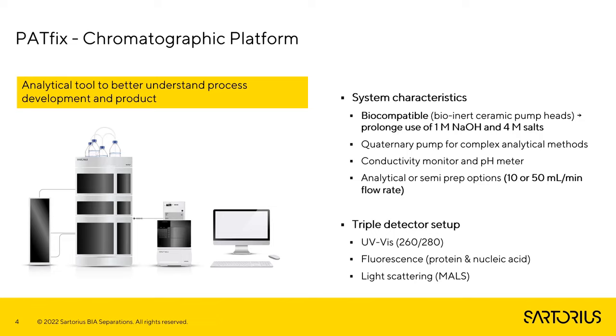Here is our PatFix HPLC chromatographic platform. We developed this platform to speed up upstream and downstream processes and help our customers develop their processes. The main features of the platform system are: wetted parts that are biocompatible and resistant to harsh cleaning conditions, such as 1 molar sodium hydroxide and high salts; quaternary pumps for complex analytical methods; and all analytical methods are based on salt or pH gradient or a combination of both. Conductivity and pH monitors are very important devices. The system can also be easily turned into a semi-prep — you just need to change pump heads to do scale-up in a lab.